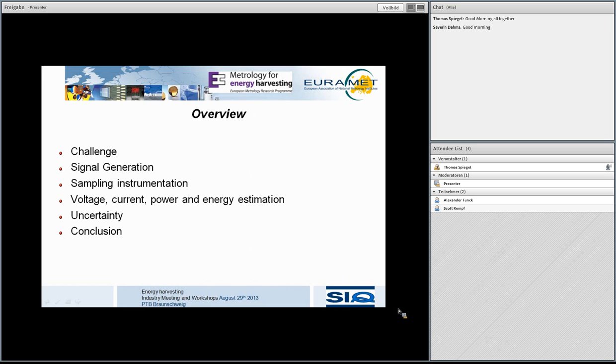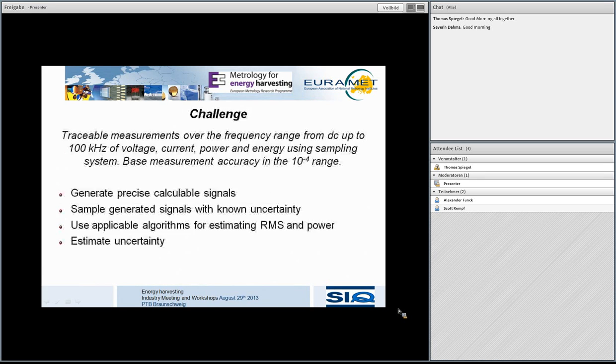and from that I would go to the problem of generating the signals which were useful for our measurements, to the sampling instrumentation used to sample these signals, to the estimation of these samples and how to calculate the power, the voltage, RMS, and the energy out of these sampled signals. And that was the main part, actually, of our work. I will tell you why. And then I will come to the uncertainty of these measurements, and I will present some conclusions on that. So the challenge was, as you already know now, to measure accurately arbitrary waveforms, signals, and their power in the frequency range up to 100 kilohertz with uncertainty of around 10 to minus 4.